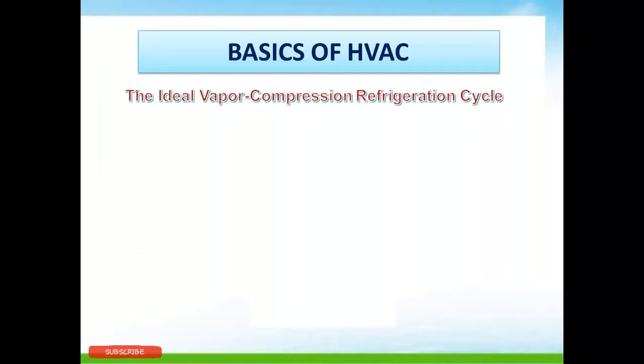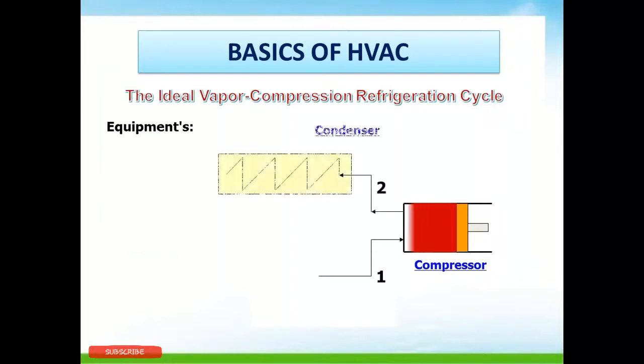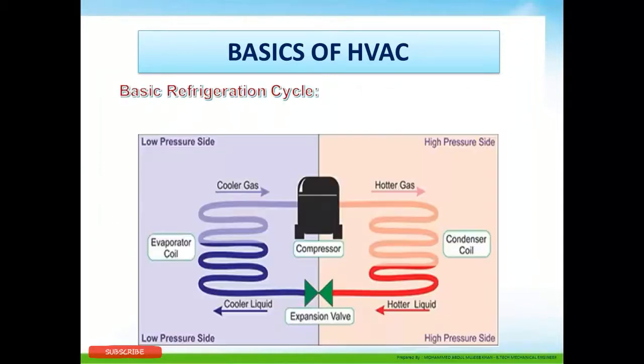Now let us understand the vapor compression refrigerant cycle. The first and major equipment in any refrigeration cycle is the compressor. The refrigerant is compressed in the compressor and then transferred to the condenser where heat is rejected - either air-cooled or water-cooled. Then the refrigerant passes through an expansion valve, and finally through the evaporator where the actual cooling happens. Two different pressures exist in a refrigeration cycle.